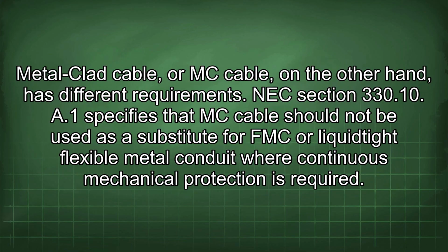Metal-Clad Cable, or MC cable, on the other hand, has different requirements. NEC Section 330.10(A)(1) specifies that MC cable should not be used as a substitute for FMC or liquid-tight flexible metal conduit where continuous mechanical protection is required.